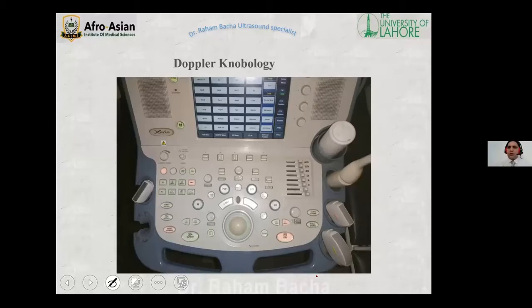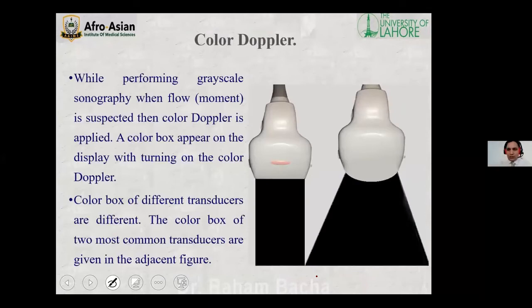So first of all, whenever we are going to perform grayscale ultrasound, we have some suspicion regarding flow. We are suspicious that maybe there will be some flow, there are some tubular structures, maybe there are vessels, so there must be some flow. So we are going to apply color Doppler on it. Whenever we apply color Doppler, we have a color box on the screen, and different transducers have different color boxes, but here I'm going to show you the two most commonly used transducers. One is the linear transducer and the other one is the convex transducer. The color box of the linear transducer is rectangular, and that of the convex transducer is trapezoid.